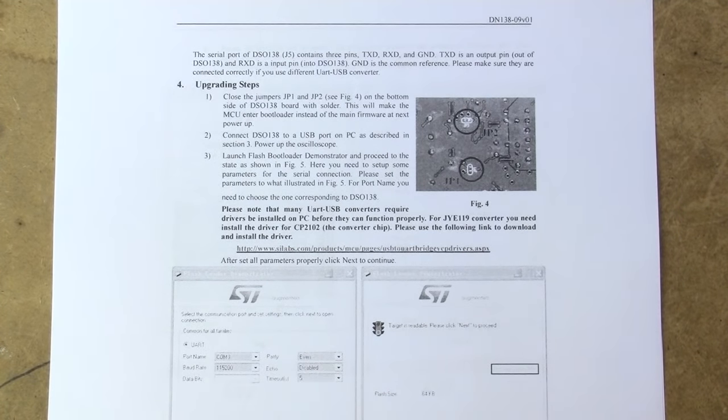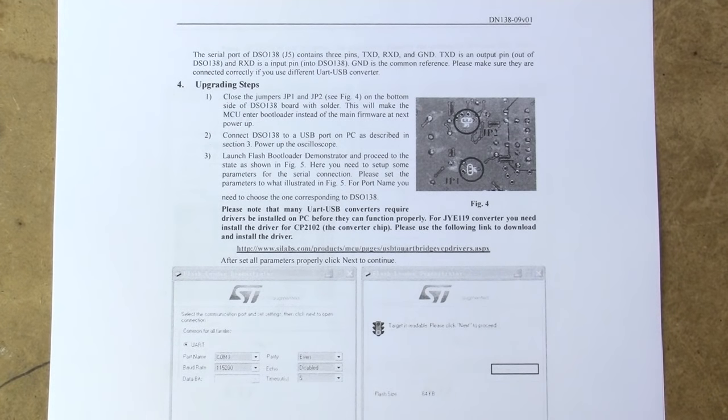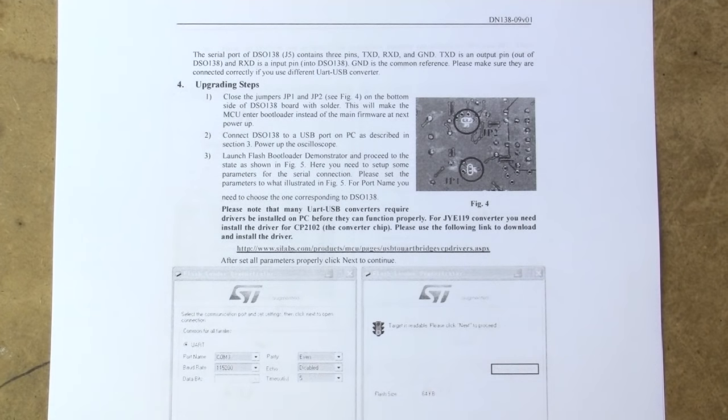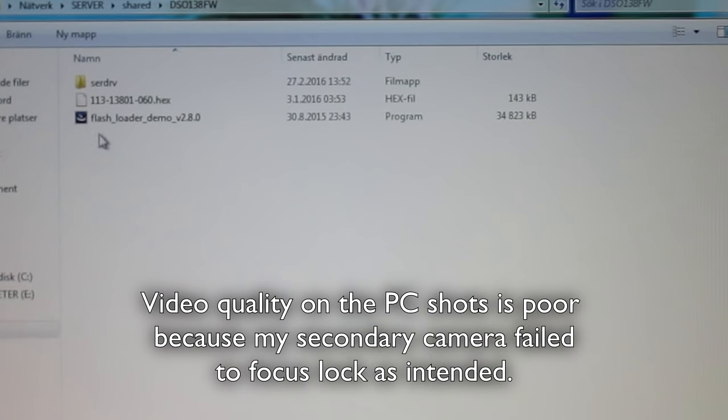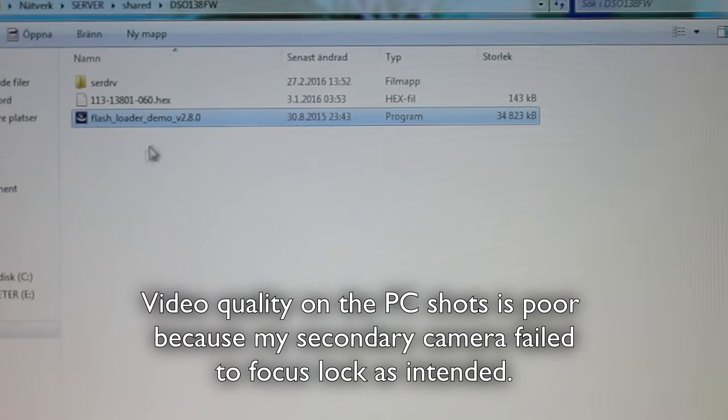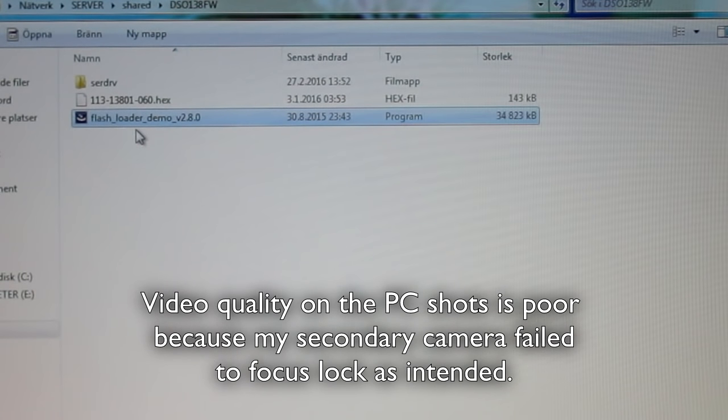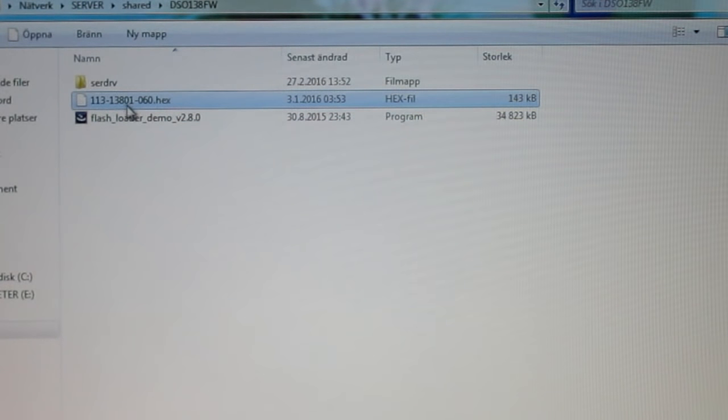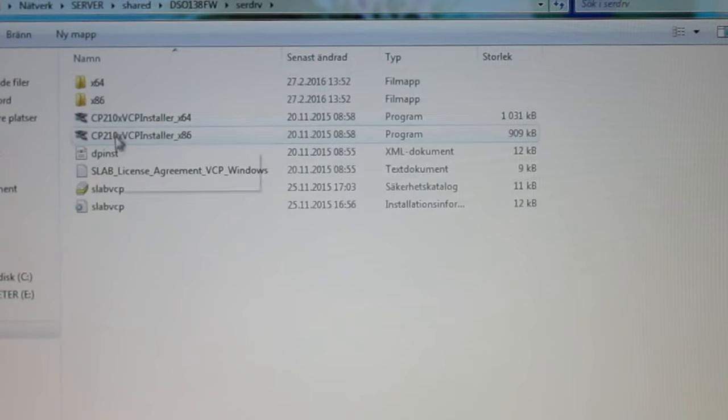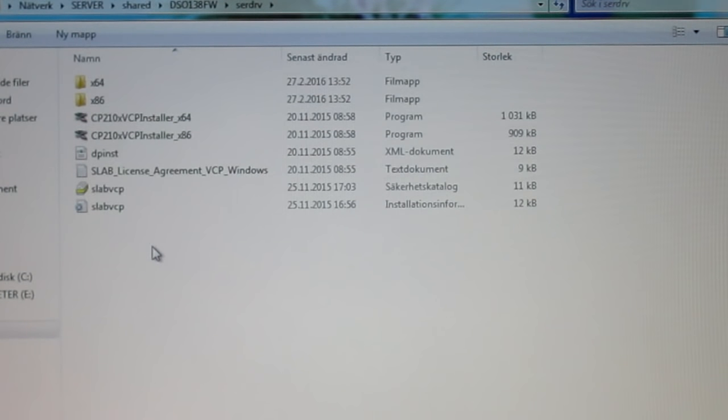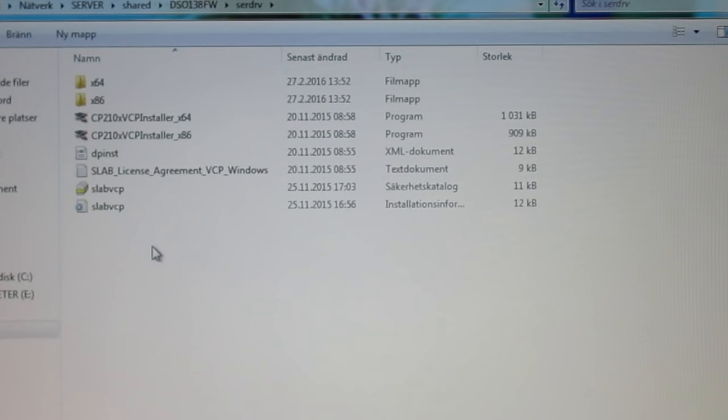The actual upgrade steps tell you to short a couple of jumpers on the device, which is going to put it into bootloader mode. And it also tells you to install drivers for your chip, and this third party link works as well. So, let's just see if we can get the software set up before we move on to the hardware and actually hooking this thing up. So here on the PC, I've downloaded the Flash Loader Demo application, which you use to actually load the software onto the DSO. I've got the hex file, which is to be loaded, and I've got the files for the serial to USB converter.